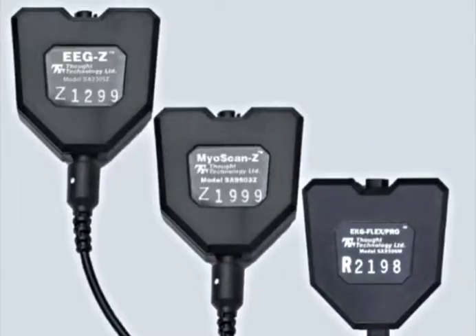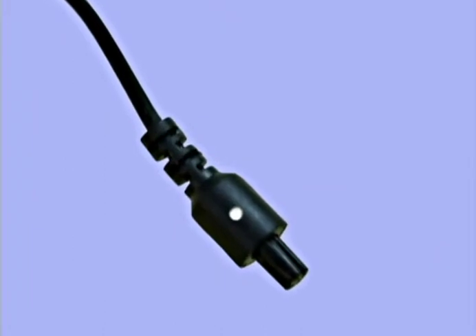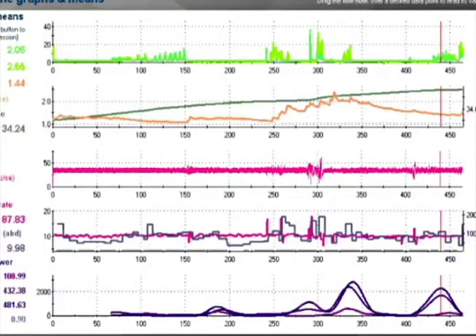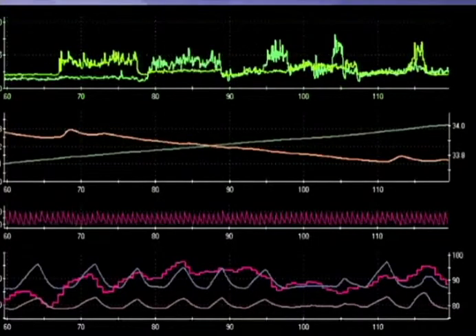Our EEG, EKG, and EMG sensors are amplified at the measurement site, instead of at the end of a long, noise-prone wire. They are connected to the encoders by a combination of custom-designed low-artifact wires and miniature glass-filled plastic connectors with gold-plated pins, providing unparalleled accuracy and durability. These cables are so strong and flexible that you can even lift the unit by the cable itself. Our overall system noise is well below 0.5 microvolts and provides accurate data — not zeroed out through software offset tricks as in other hardware with significantly higher system noise. Low noise is essential for differentiating and enhancing low-level EMG signals.